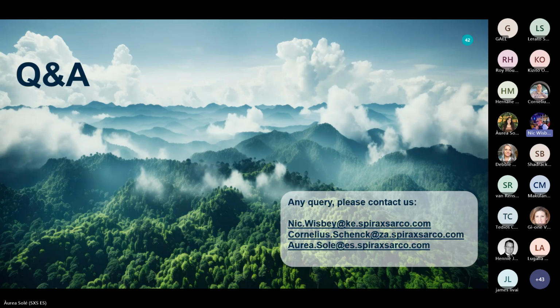I'm sorry, I think I may have cut you off, so I don't know if you have more to add. Yeah, no, normally that's it, what Nick has mentioned. Normally as well, in the audits, we are providing an energy and mass balance to get more or less the temperature in which we are returning the condensate, as well as the steam generation. There's a calculation being done, but that's just an estimation. It's not the accurate level that a meter would tell us, basically. And that's for the overall condensate return percentage estimation.